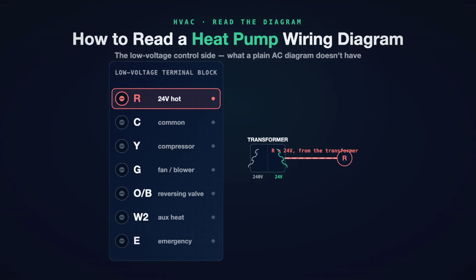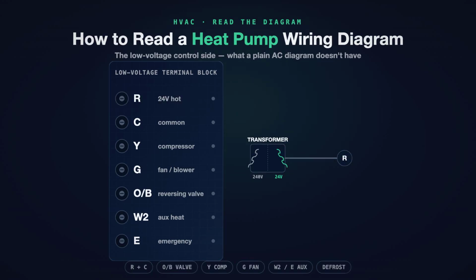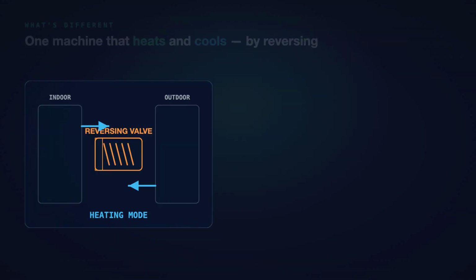Now, if you have read a regular air conditioner or furnace diagram before, some of these letters look familiar. But a heat pump adds terminals a standard system simply does not have, and those are exactly what we will decode. This is how to read a heat pump wiring diagram, aimed at the low voltage control side that actually trips people up. So what makes a heat pump diagram different?